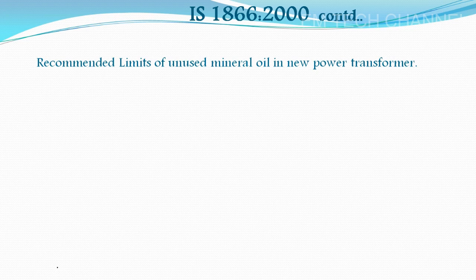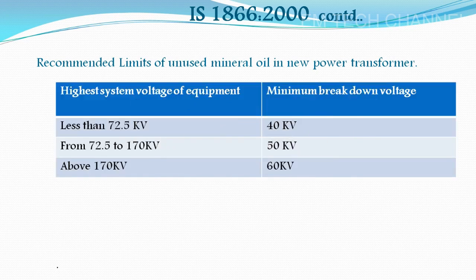I already said before, mineral oil is a generic name, and up to 72.5 kV of highest system voltage, minimum breakdown voltage should be 40 kV, and from 72.5 kV to 170 kV, the minimum breakdown voltage should be 50 kV, and above 170 kV, the minimum breakdown voltage should be 60 kV.